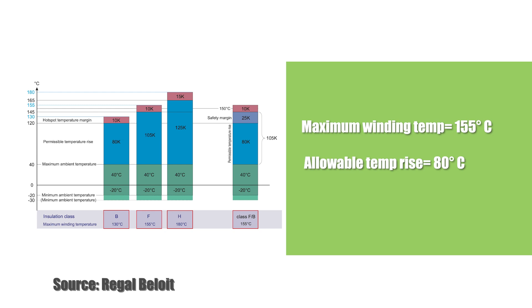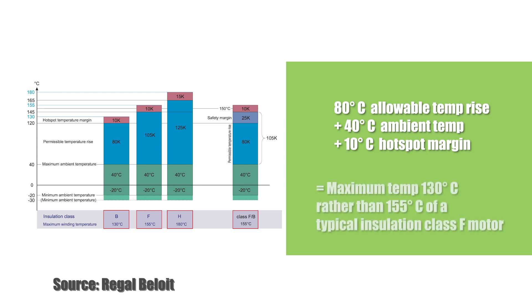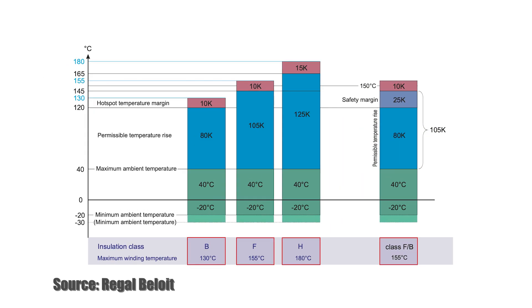Adding 80 degrees C to the ambient temperature of 40 degrees C, plus the 10 degrees C hotspot margin of insulation class F, gives a maximum temperature of 130 degrees C, rather than the 155 degrees C of a typical insulation class F motor. This means that the F slash B motor has an additional 25 degrees C safety margin, which can provide significantly longer insulation life, and therefore motor life.